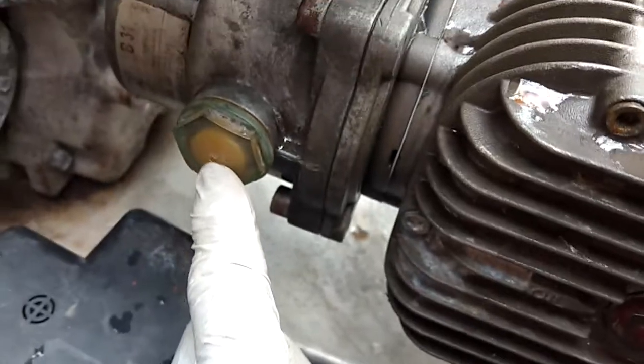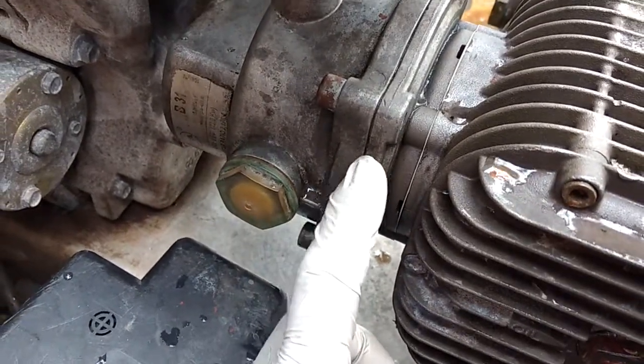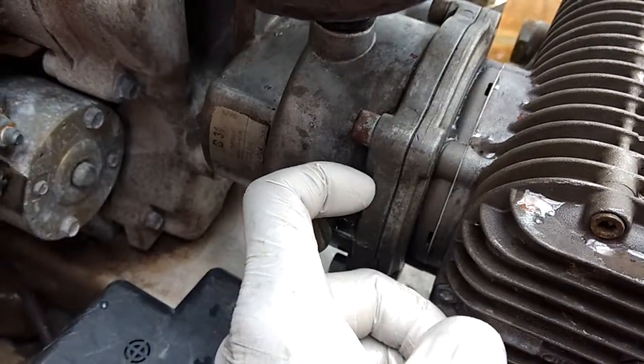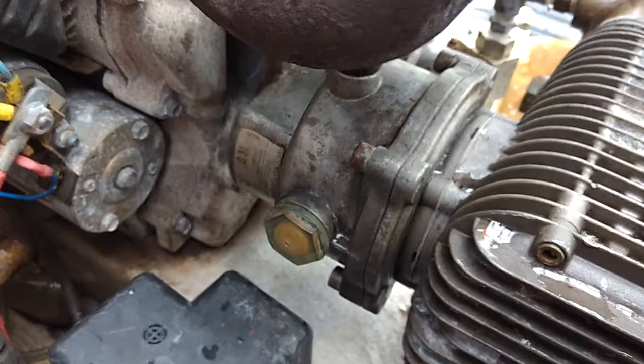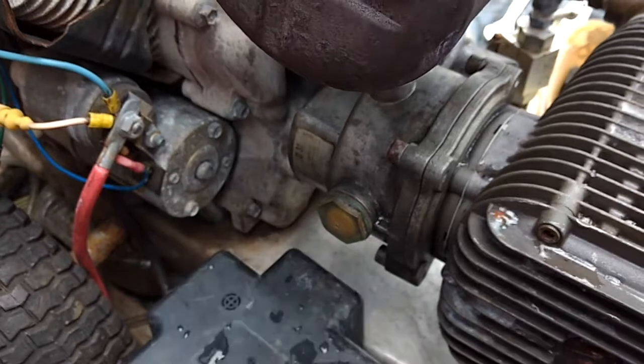The oil is very turbulent here. The oil seal has more work to stop the pressure from inside the gearbox going back into the pump. Although there's a venting cap, there's a lot more turbulence inside the gearbox oil.